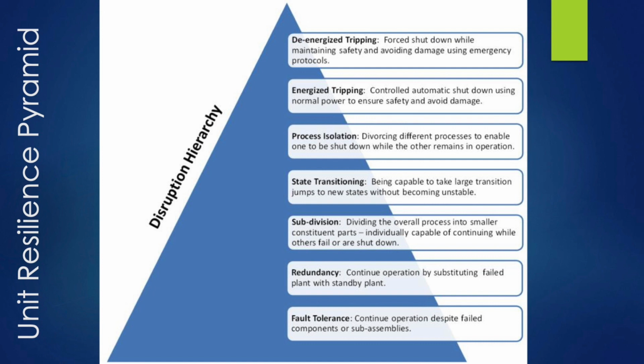Process isolation has to do with being able to shut down a specific process at the plant while other processes remain in service and continue to operate. A good example would be at a coal power station, where you can trip the turbine but the boiler would remain on load. If the cause wasn't in the boiler area, there's no point in shutting the boiler down, unless you didn't have this capability. Otherwise keep it on load, it will enhance return to service.